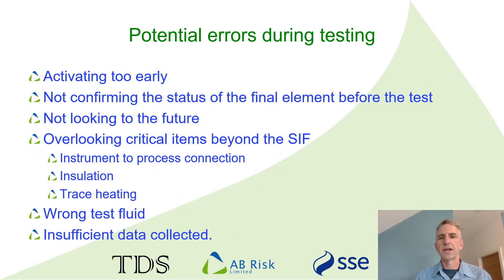We've identified a number of potential human errors that can occur during testing that can compromise the value of doing the test in the first place. Some are obvious, some less so. If the final element is not routinely operated, we need to confirm that it will operate on demand within the necessary time. It's not unheard of for technicians to predict that the valve may stick, so they exercise it a few times so that when they do the test, it passes. This is often a learnt behaviour from previous tests where it seemed slow to activate, but they found if they repeated the test a couple of times the problem cleared. Clearly, that's not what we need to know — if that's a problem, we need to know the valve sticks and do something about it.